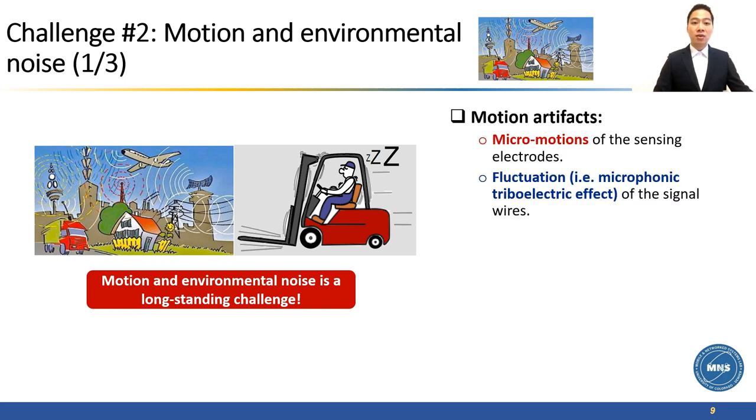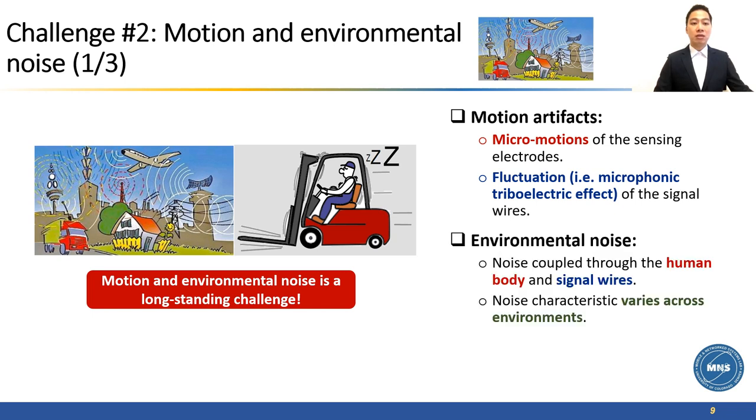One of the most important challenges of designing a reliable wearable device is to cancel out the noise created by human motion and coupled from the environment. From our in-lab experiment, we can observe that environmental noise can have a significant impact on the captured signal, while motion can completely distort the signal. According to the literature, there are two main sources of motion artifacts: micro movement of the sensing electrodes, and microphonic triboelectric effect of the signal wires. They lead to the fluctuation in the electrical pathway, resulting in noise. Radio and electromagnetic interference from various appliances can be easily coupled into human body and signal wires which act as antennas. To make it more challenging, depending on the environment, the noise could vary. So a solution also needs to work across different environments.